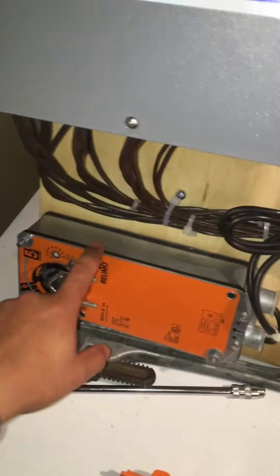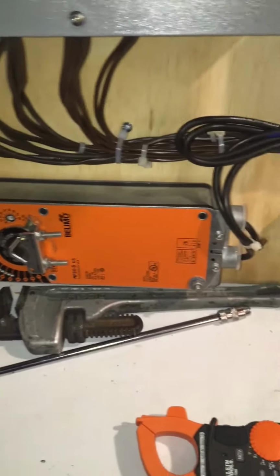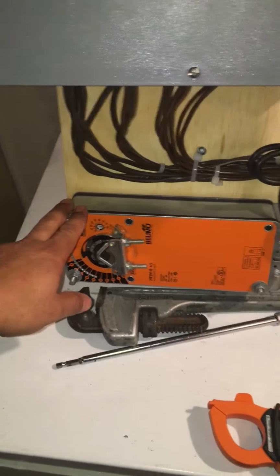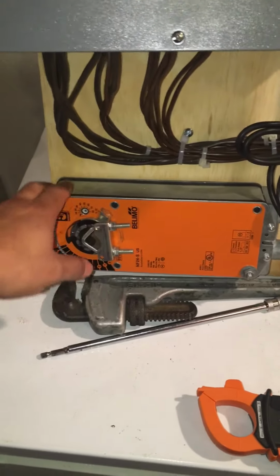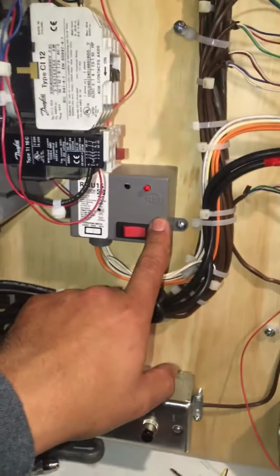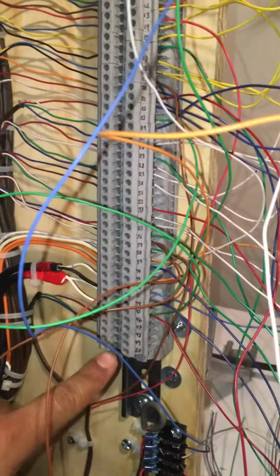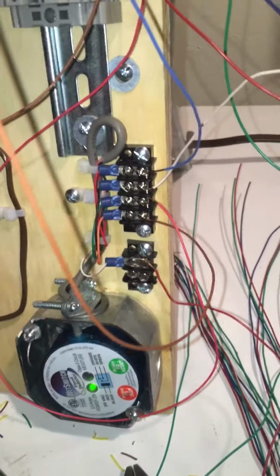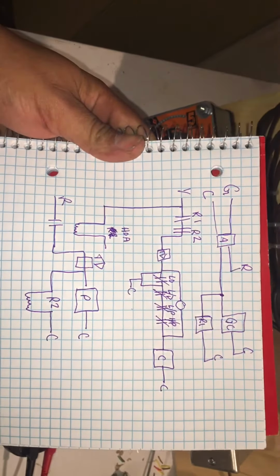Down here we have a Belimo actuator with an end switch on it, which I'm using as a supply air damper interlock for the fan. Here we have an HOA rib relay, leak detection, and then this is our terminal strip, which is marked from 1 to 50, and this is for the leak detection terminal strip. In short, basically this was the schematic that I made, just rough, of what all of that is.